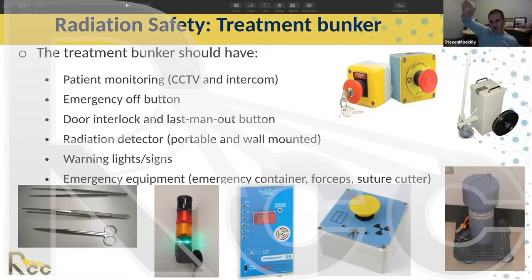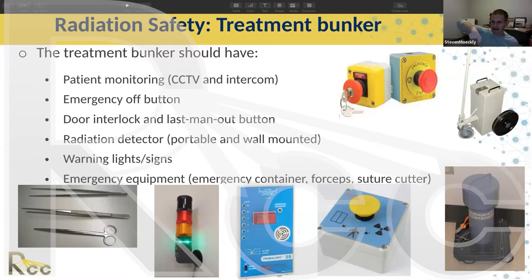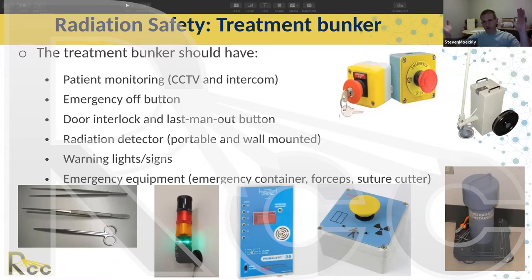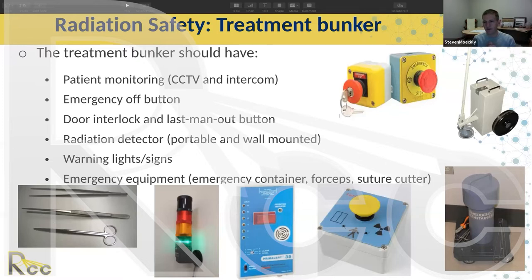We chose the shorter forceps because we felt we'd be more adept at grabbing the source wire with them, spending less time in the room. As long as you're trained on your chosen tool and can use it effectively, that's fine. One thing I don't include in emergency equipment is a wire cutter. You should never cut the wire — cutting it will only lead to problems, and would only ever be done by a service engineer after everyone has left the vault.